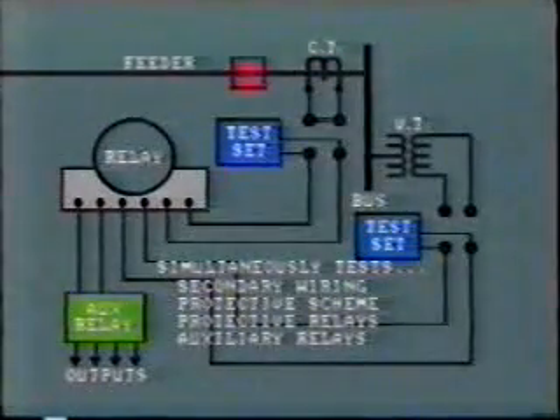Injection of the appropriate value of secondary current and voltage to simulate differing fault conditions will allow us to simultaneously test the secondary wiring, the protective scheme, the protective relays, auxiliary switches, and the resultant functions. Remember, in any particular protection scheme, several protection relays may be involved and several secondary inputs required to simulate fault conditions. Each functional test will need careful, detailed planning before execution.